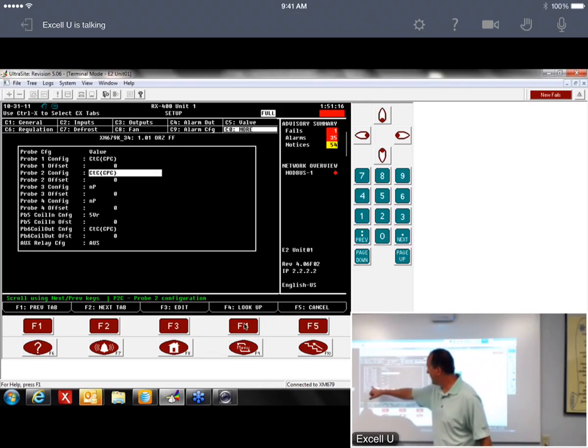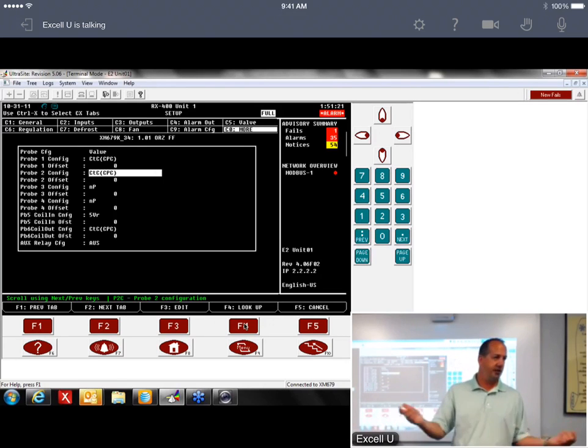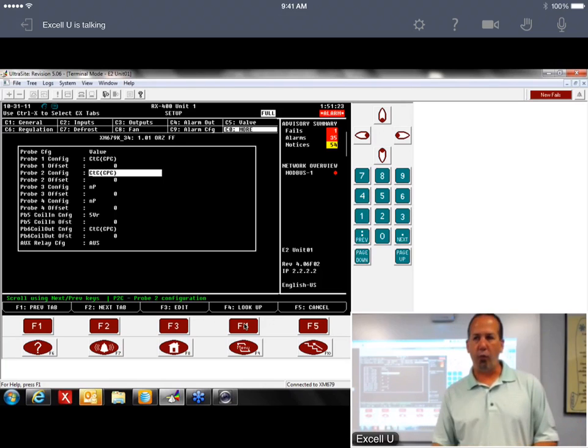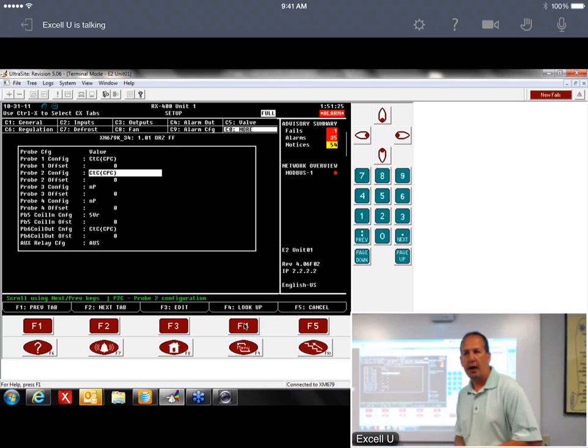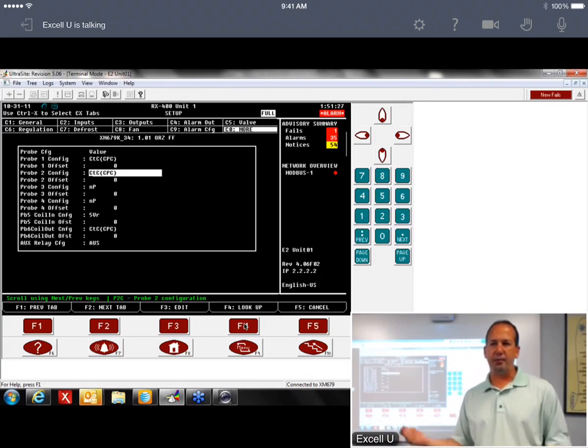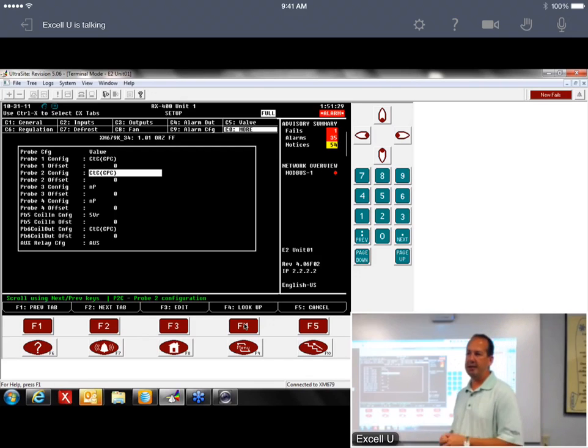The transducer here on PB5, that's our suction transducer. 5VR is our 1 to 5 volt transducer. There's other options, 4 to 20 milliamp, all that kind of stuff. But yeah, the CPC one that we use is the 5VR.